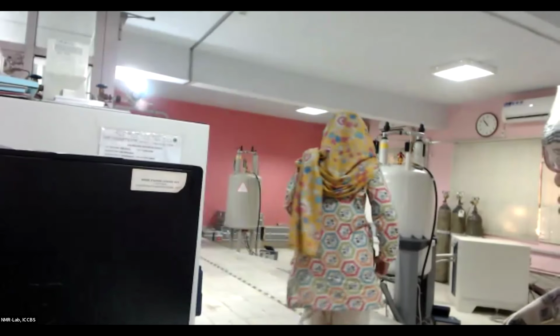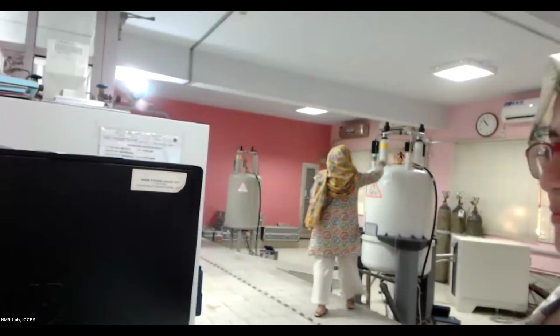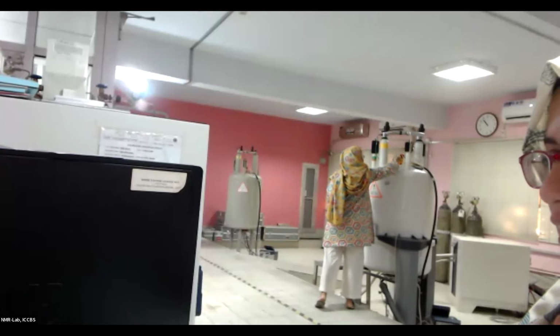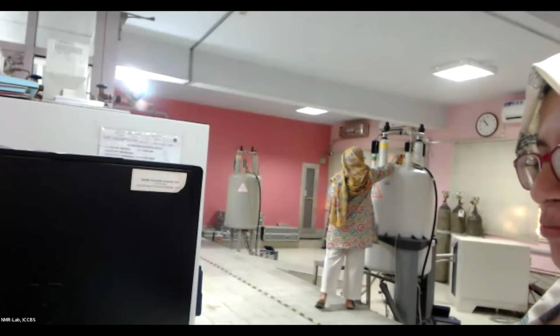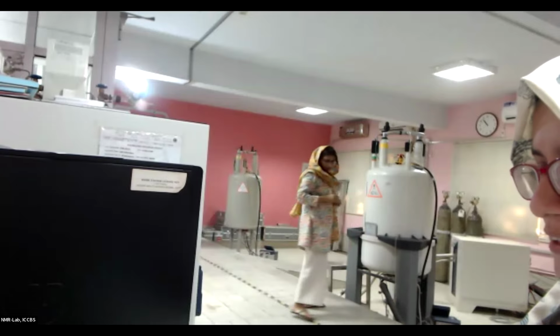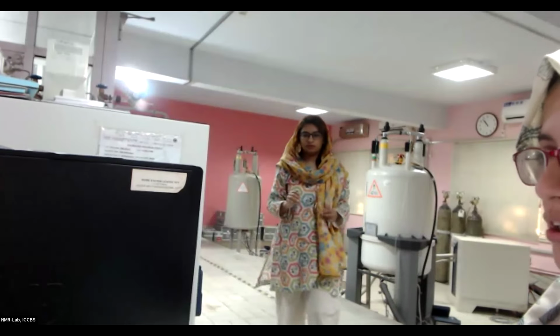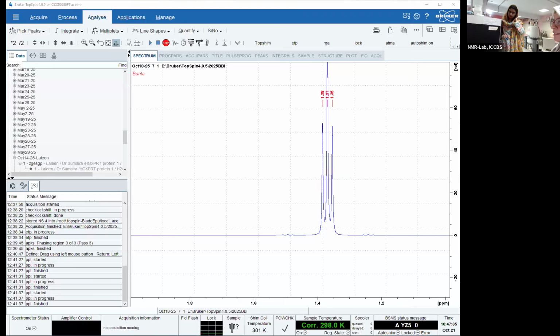So kindly remove that, Dr. Humaira. After it is removed, I'm going to share the screen of the TopSpin software, where I'm first opening the BSMS board, from where I will give the command to lift the sample inlet.